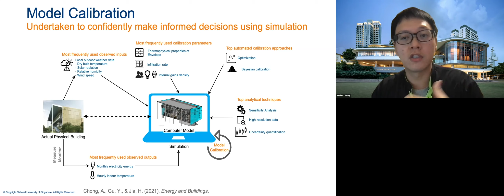Parameters that are often calibrated include the thermophysical properties of the envelope—things like the U values of your walls and windows, infiltration rate, which is known to be very uncertain, as well as internal gains stemming from things like occupancy, lighting power, and plug loads.